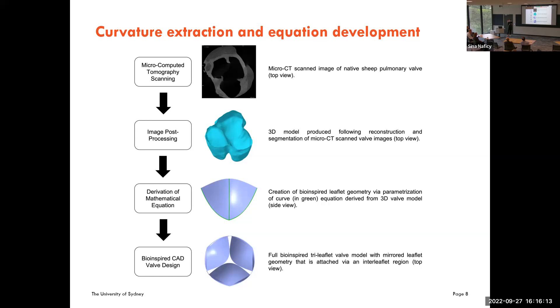This 3D model can be manipulated and modified on computer-aided design (CAD) software. We identify the best-looking leaflet out of the three, because symmetry is important both for valve design and for fabrication and testing — we don't want asymmetry with the valleys and hills you would see in a native heart valve.